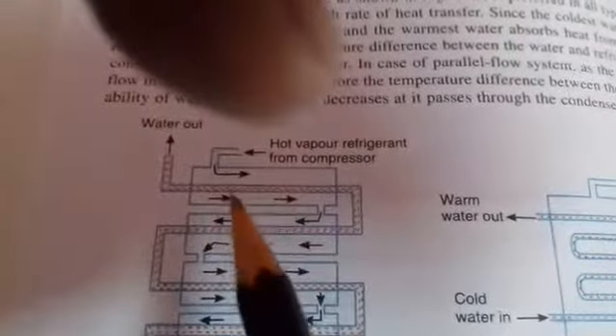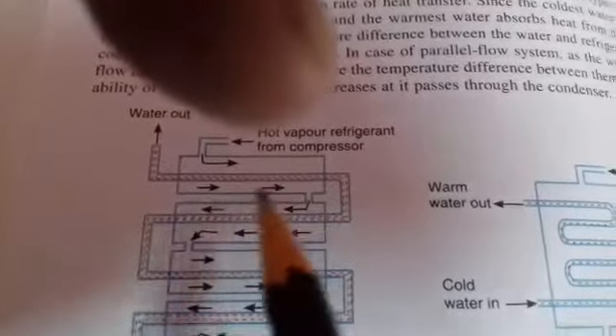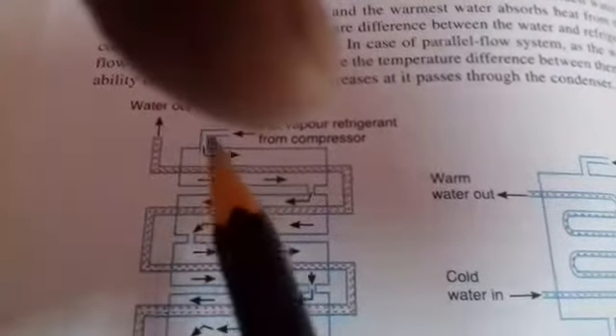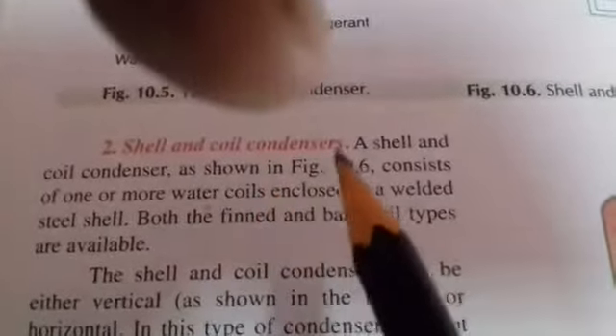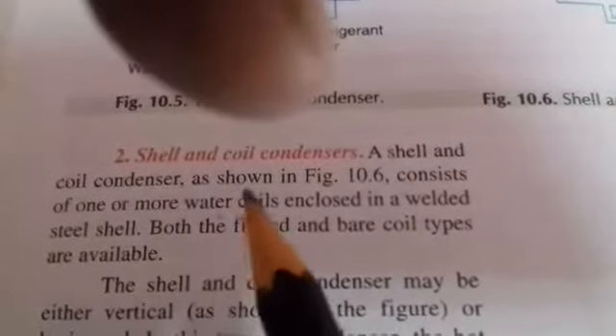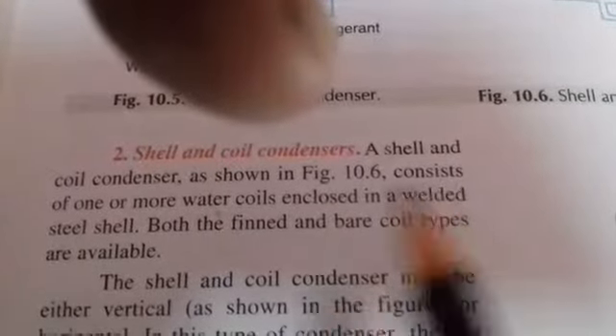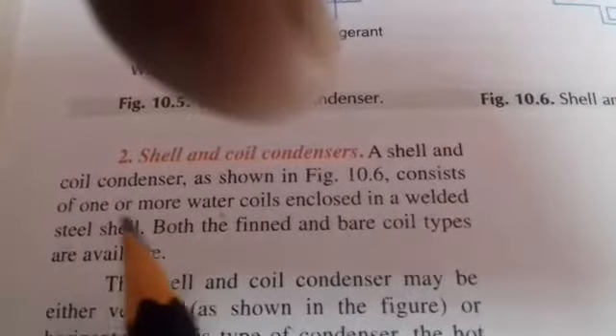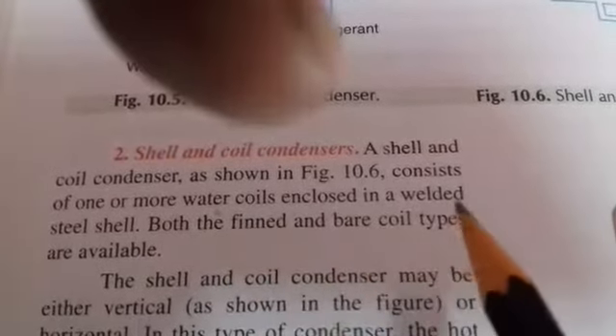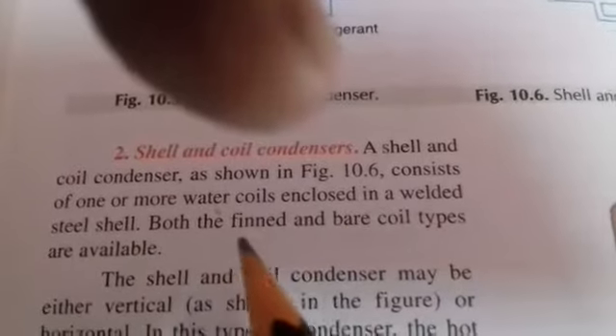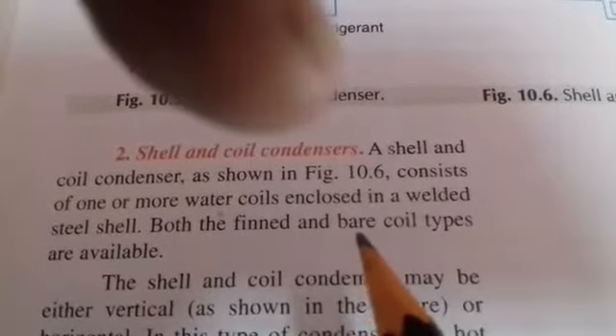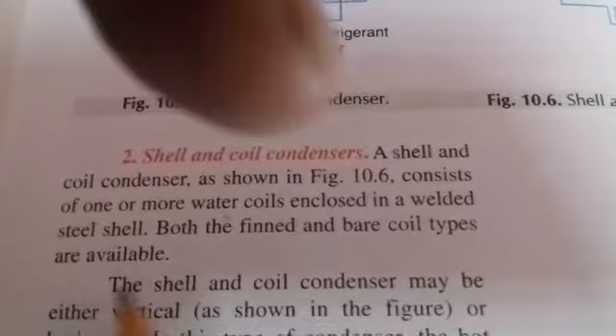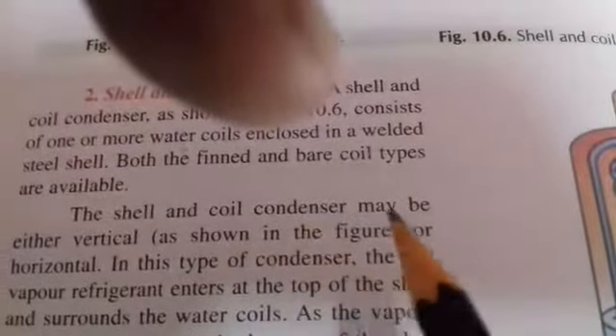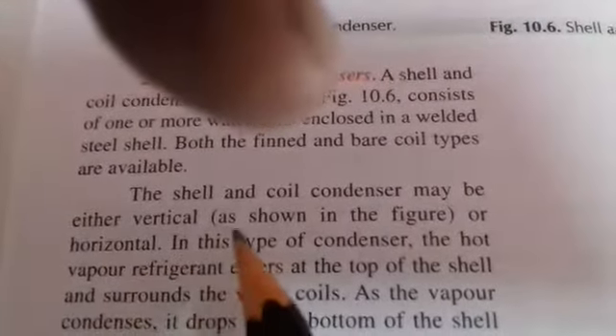A shell and coil condenser, as shown in figure, consists of one or more water coil enclosed in the welded steel shell. Both the finned and bare coil type are available. The shell and coil condensers may be either vertical or horizontal. In this type of condenser, the hot vapor refrigerant enters at the top of the shell. As the vapor condenses, it drops to the bottom of the shell, which often serves as receiver.